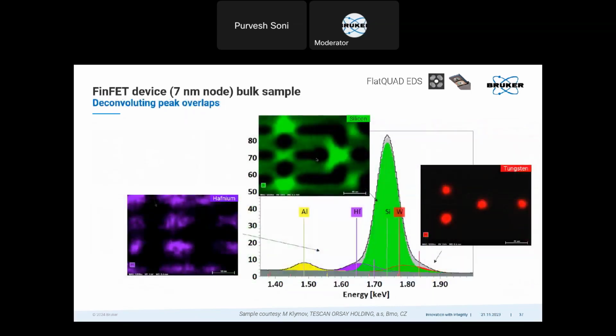And if you're working with semiconductors, then you know that there is a very strong overlap between silicon, hafnium, and tungsten at around 1.7 keV, and we could easily deconvolute this with Bruker ESPRIT software. So this is an inbuilt function in Bruker ESPRIT software. You just do one click, and the maps are deconvoluted automatically for you.